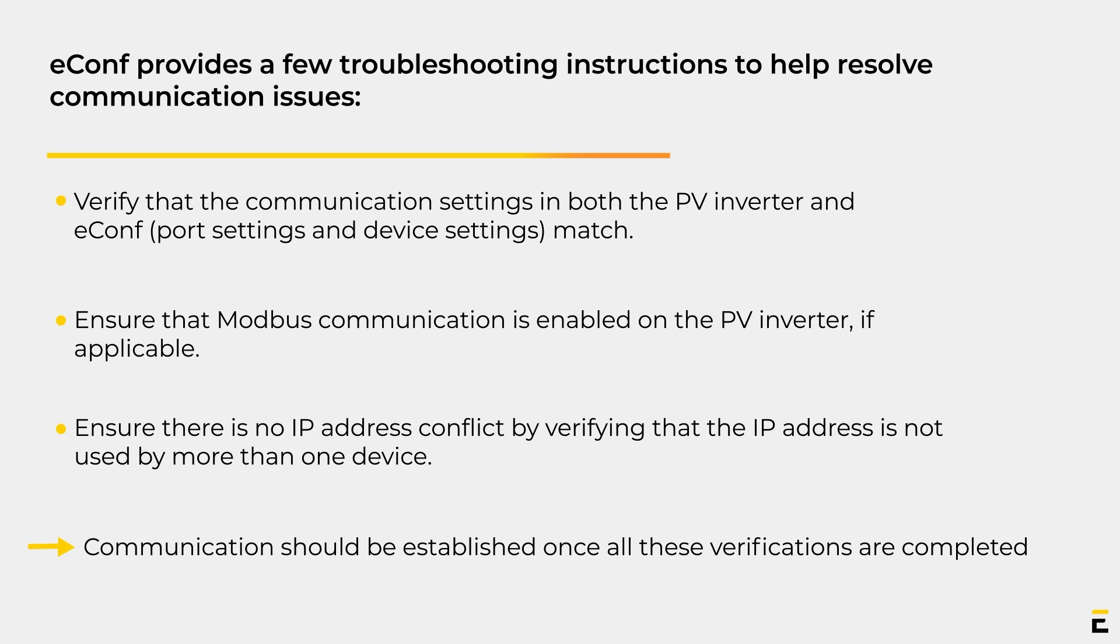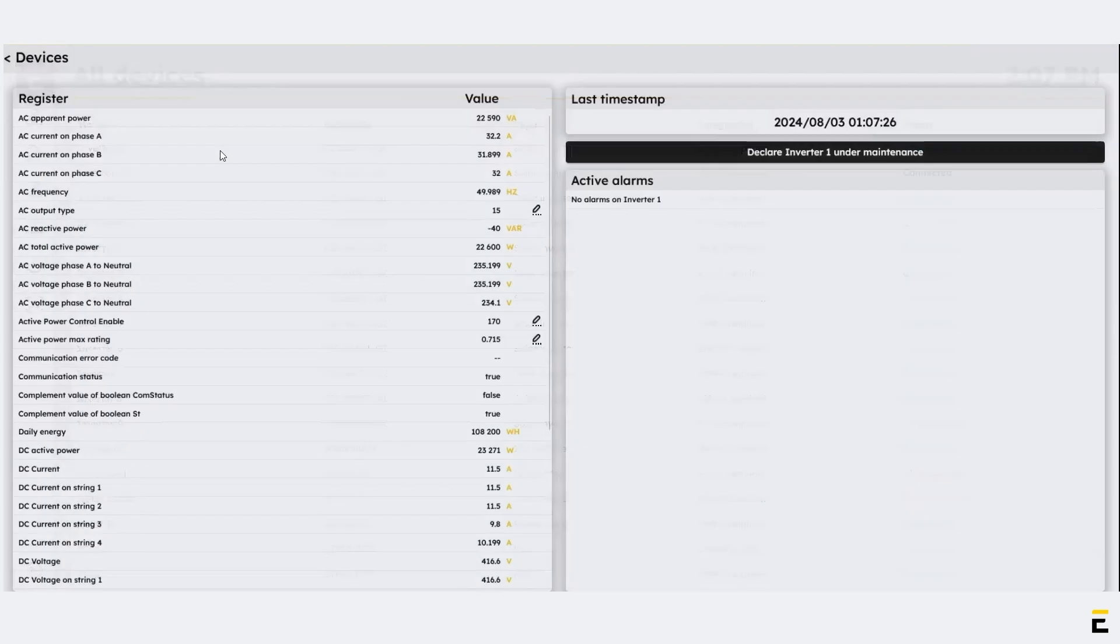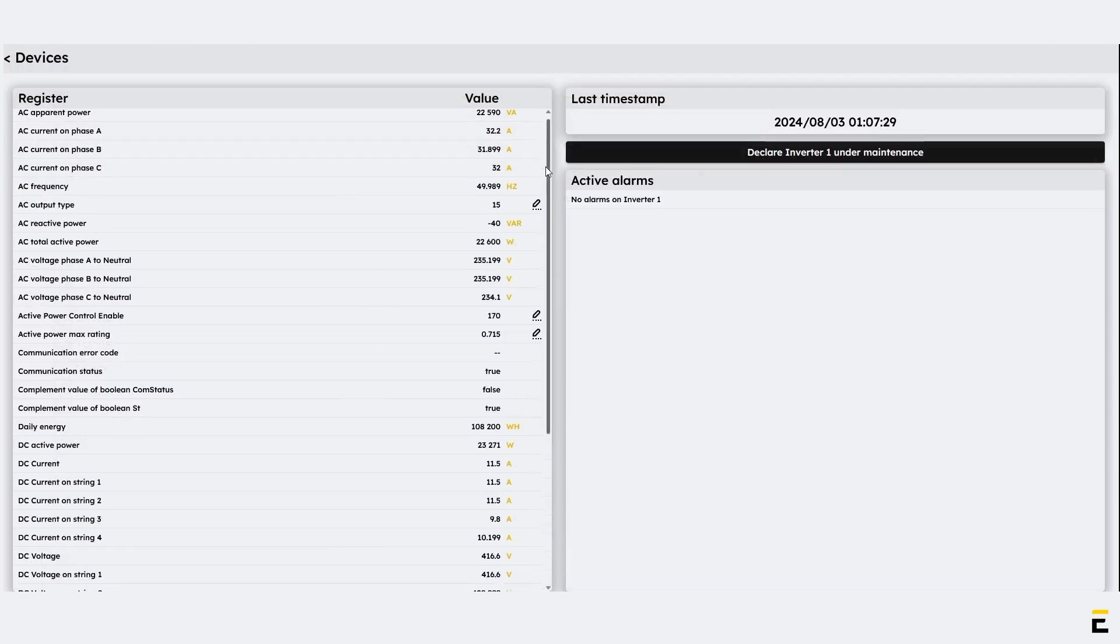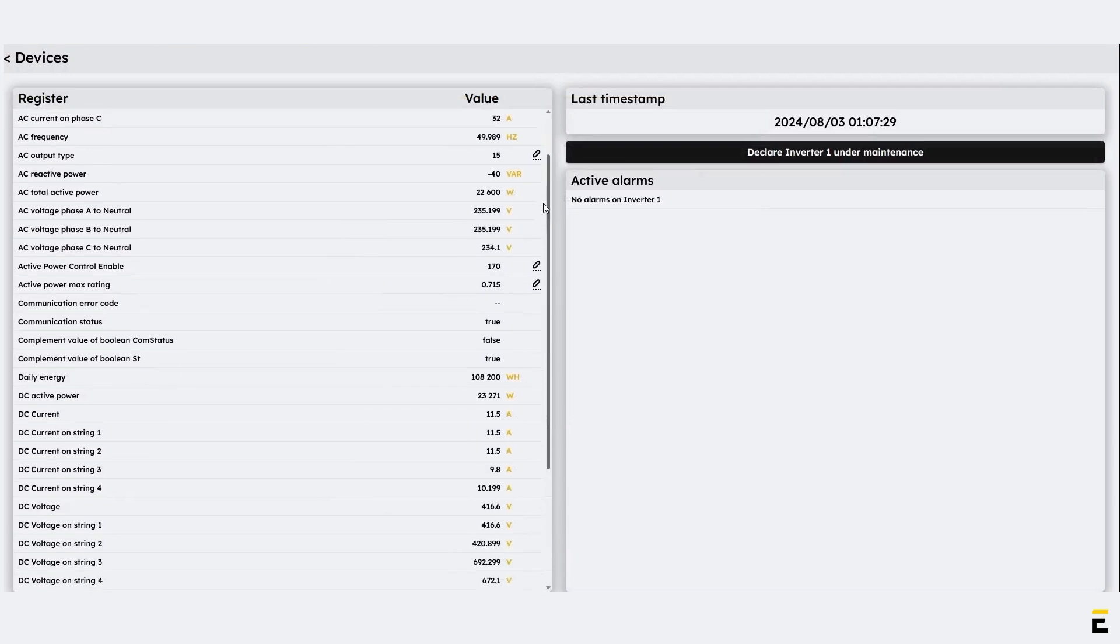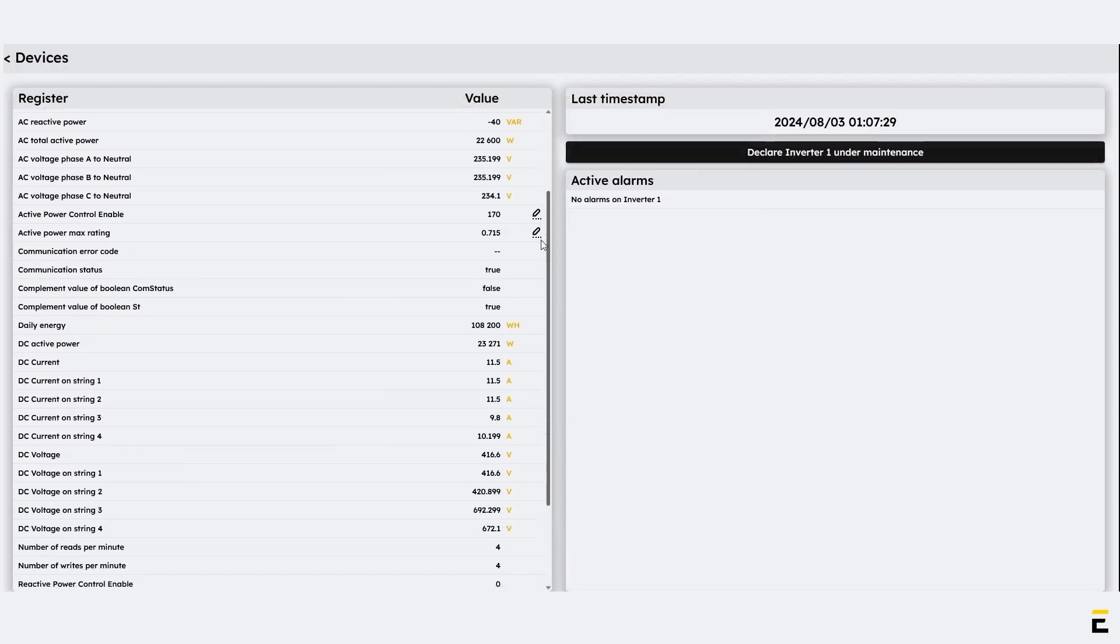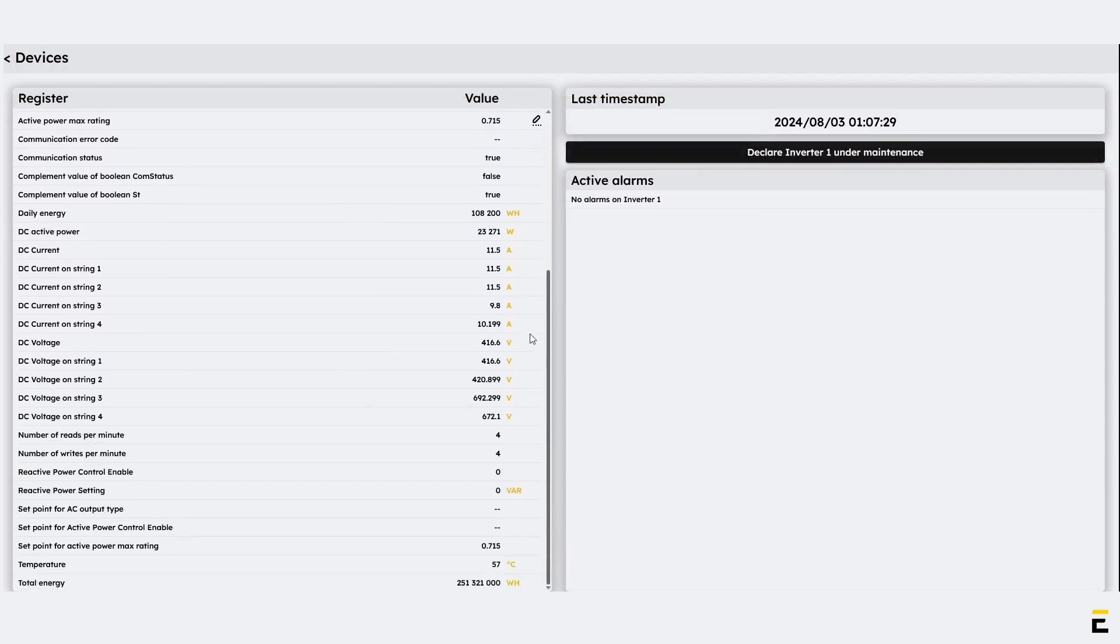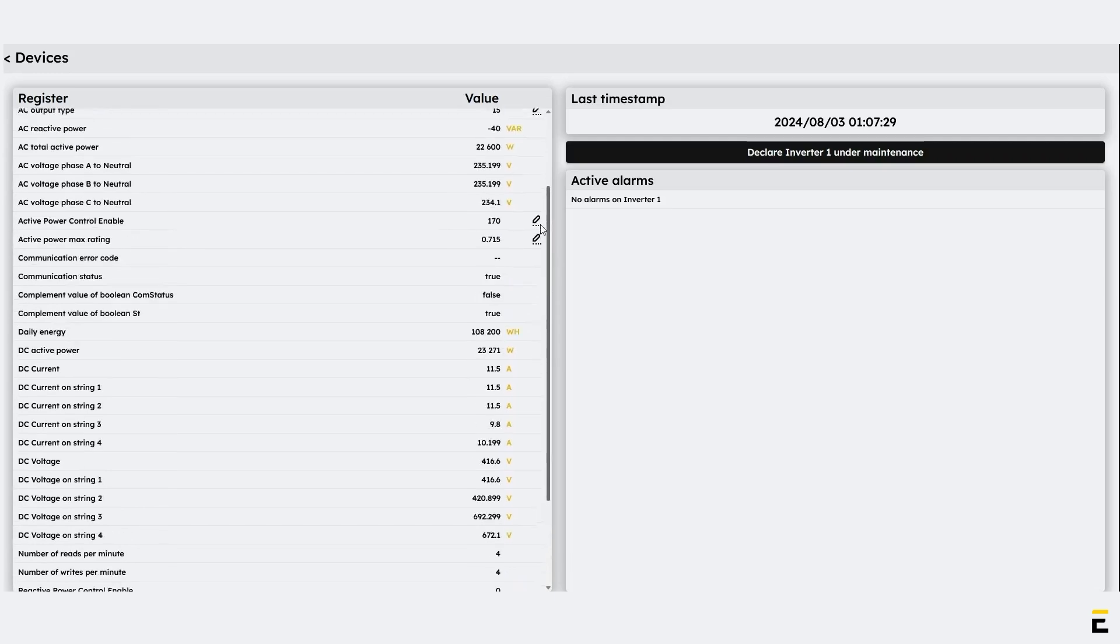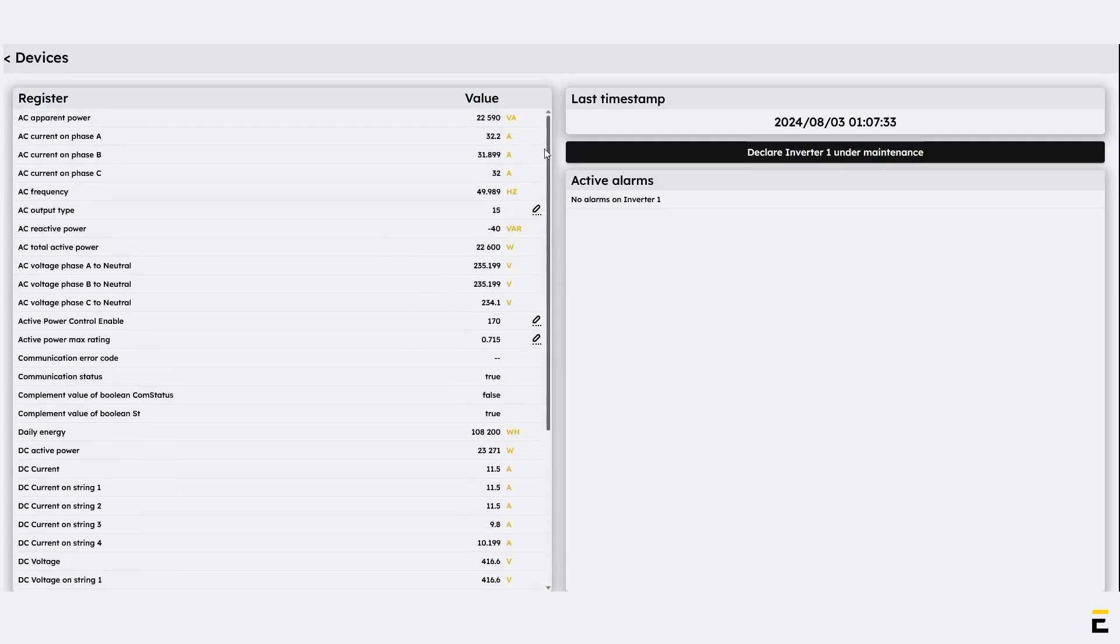As a second step of connection testing, let's verify the data acquisition. Navigate to All Devices from the left sidebar. Click on the recently added PV Inverter. The page displays all the data that the controller will read from the PV Inverter. Cross-check all the read values with those displayed on the PV Inverter itself, if applicable. The controller must receive accurate data to prevent issues in control scenarios and setpoints.